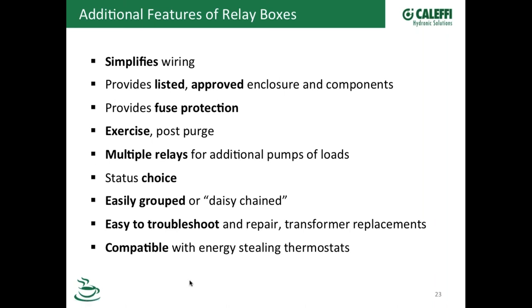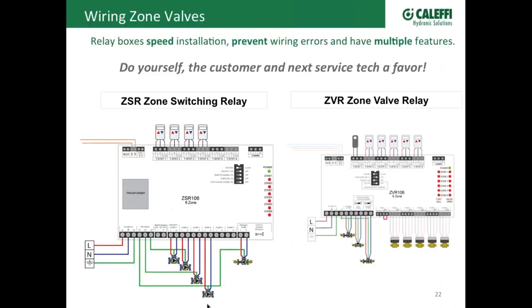We do have on our box, and you can see this, three connections for the thermostat. So you've got a common wire, I guess that one right there. So there's your red, your white, and your common. If you need power out to the thermostat to keep it powered up, as long as you have wires going out to it, we're giving you that connection right at the board, so you don't have to go in and get into your transformer with a wire nut somehow to get your thermostats powered up.